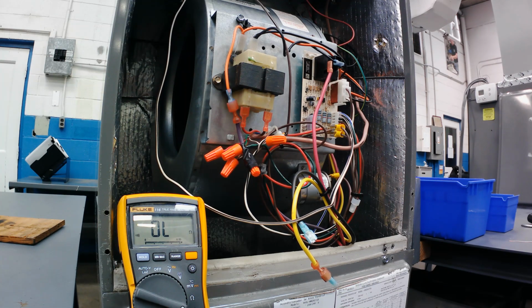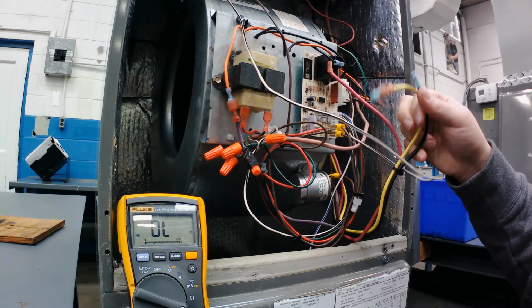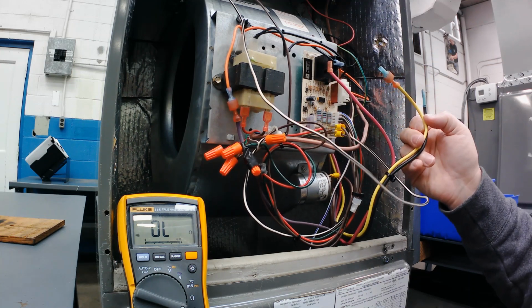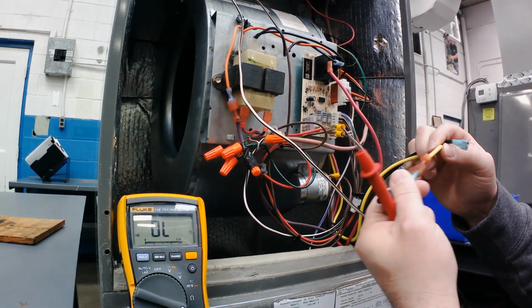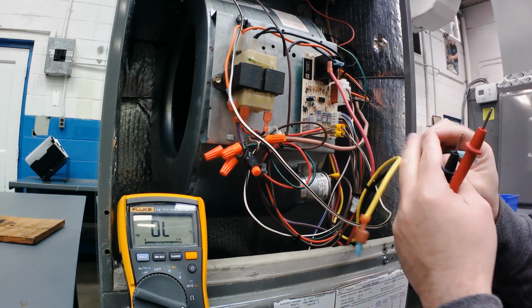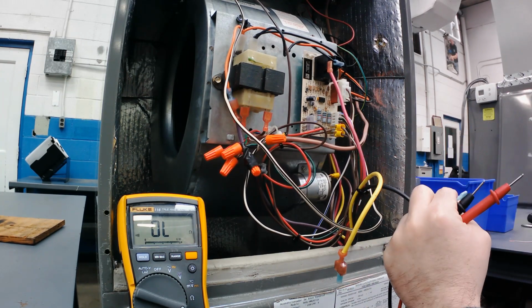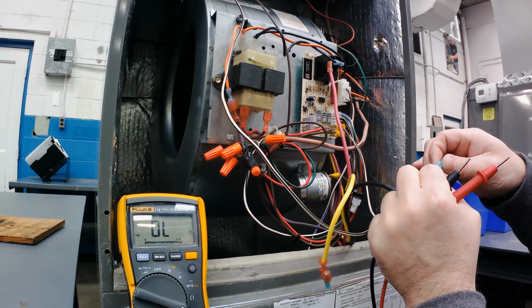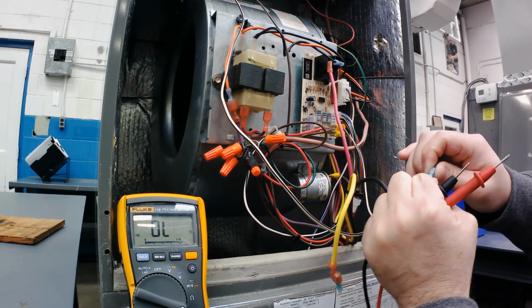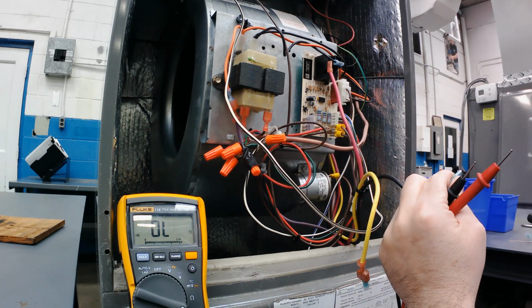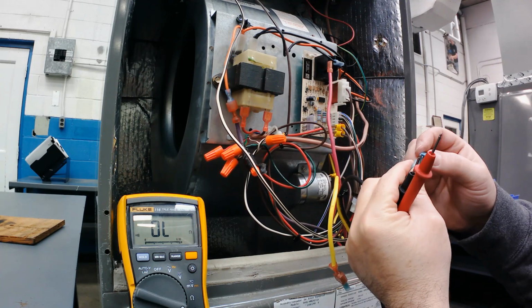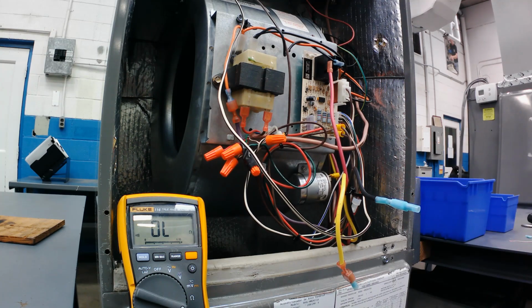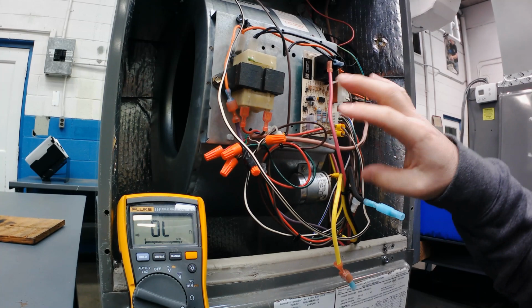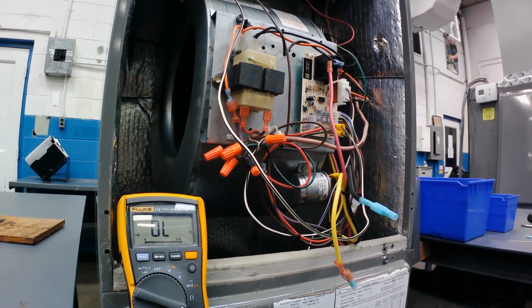Hopefully it helps. Of course, this is what happens when you don't have the proper terminals. You have just dangly wires. We decided to put some insulated terminals in the end. That way it doesn't touch that coil or the cabinet or anything like that, because these leads, even though they're not connected to anything, are still electrically hot. They're all part of the run winding on this PSC motor, so when one gets power, they're all going to have power on them too. So anyway, that is pretty much it.